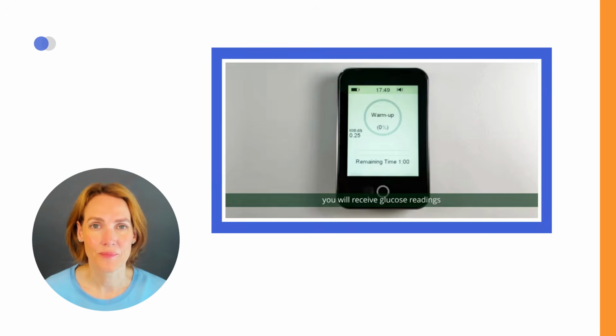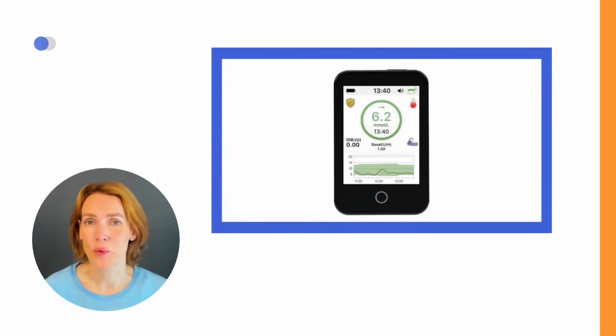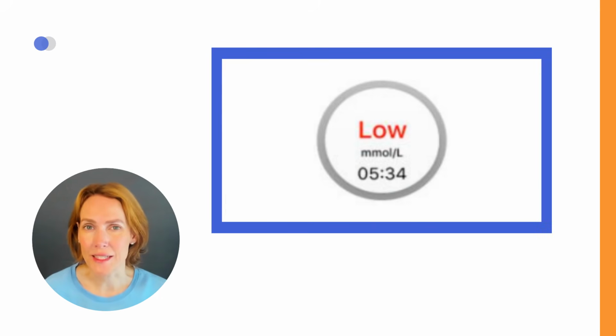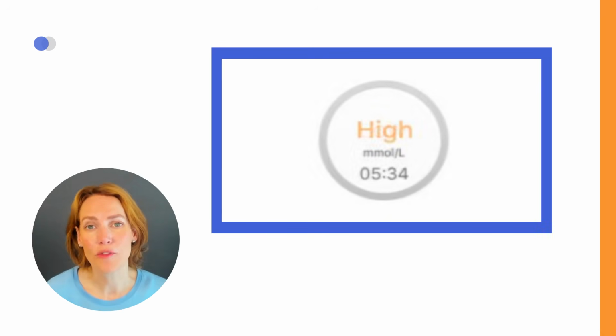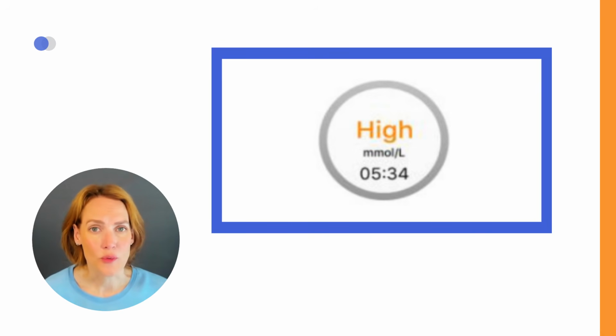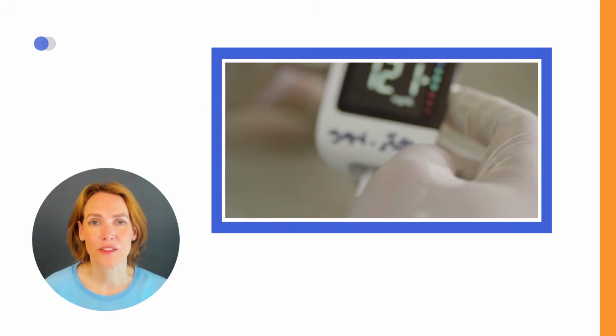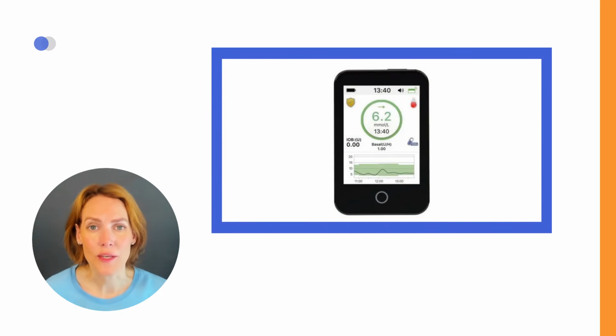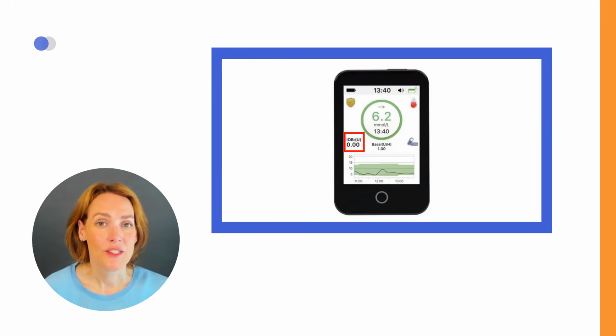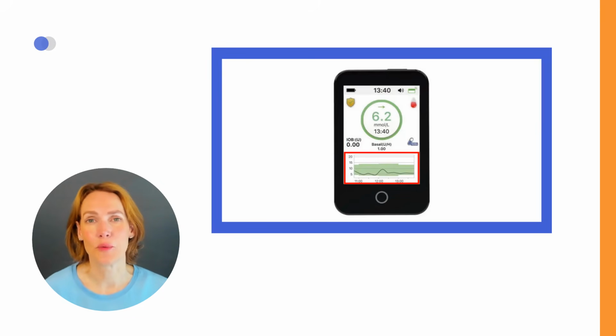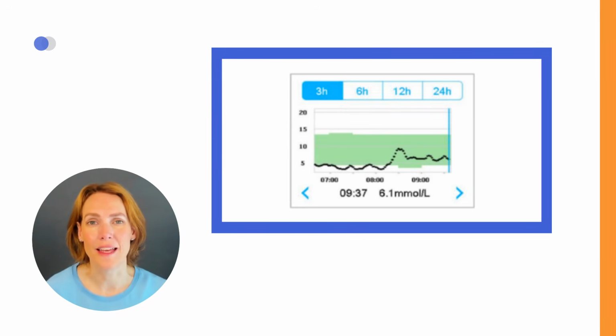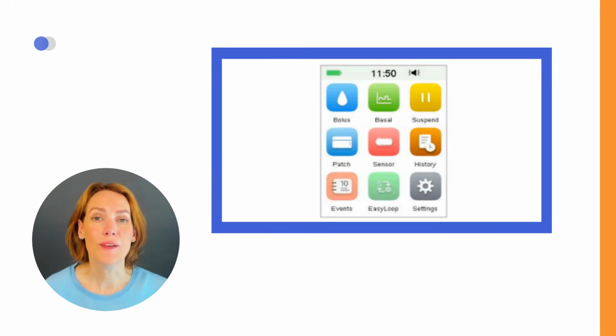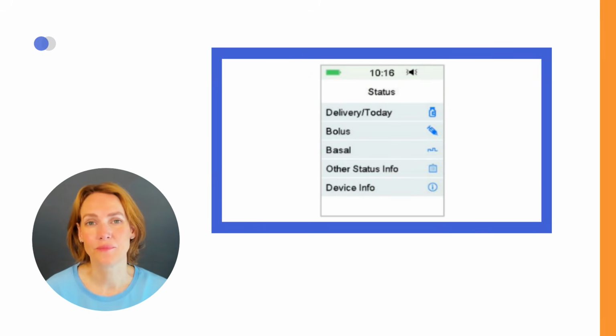On your main screen, you'll see your current glucose level along with a trend arrow. If your reading is below 40 milligrams per deciliter or 2.2 millimoles per liter, it will show low. And if it's above 400 milligrams per deciliter or 22.2 millimoles per liter, it will show high. Always double-check these extreme readings with a fingerstick and act accordingly. The home screen of the PDM also shows an estimate of the insulin you still have on board and a glucose trend graph shown below your current reading. You can also long press the trend graph to open a larger view in landscape mode. Swipe left to open the main menu, or swipe right to see the status screen.